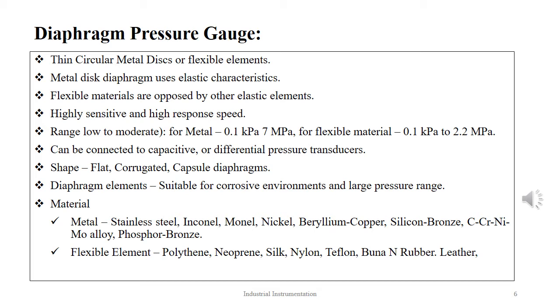The device is mainly used in low to medium pressure measurement. The device is connected to capacitive transducers or differential pressure gauges for output readout. The diaphragm can be flat, corrugated or like a capsule. Sometimes multiple capsules are cascaded together to enhance the measurement range. The diaphragm can handle corrosive environments and it is also suitable for slurry services.